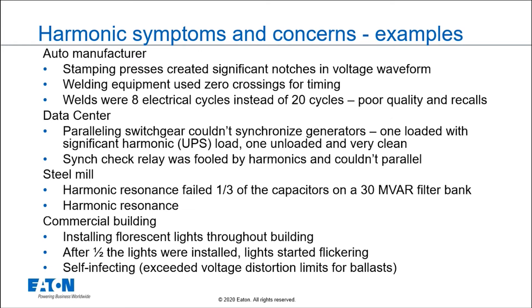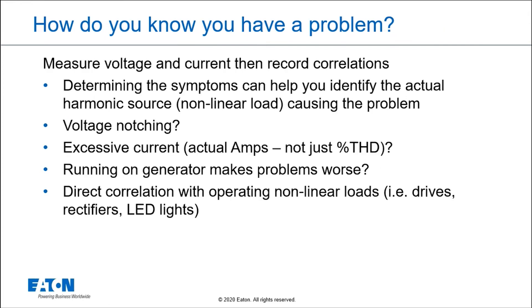In the steel mill example, there was a 30 megavar capacitor bank, and about a third of it — 10 megavar — failed because of harmonic resonance. In the commercial building, as more and more fluorescent lights were added, the fluorescent lights were self-infecting and caused those lights to flicker. So you stop and ask: the symptoms are telling me I have a harmonics issue — do I filter the harmonics, or do I rip out all the lights and install better ones?